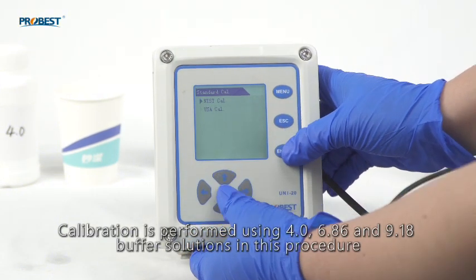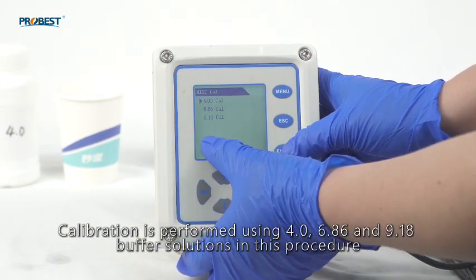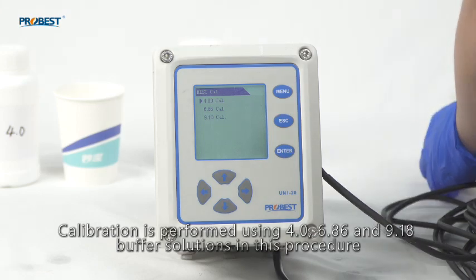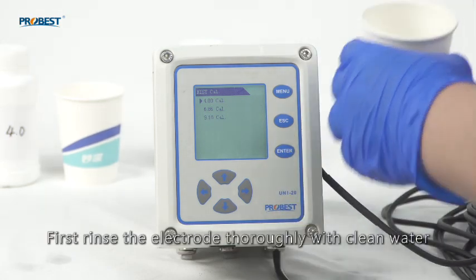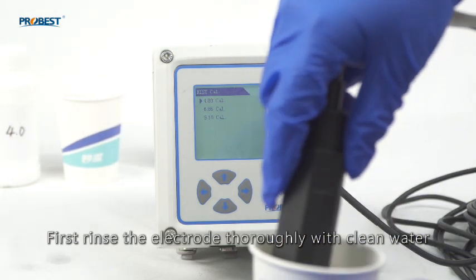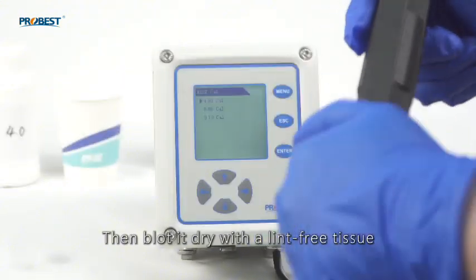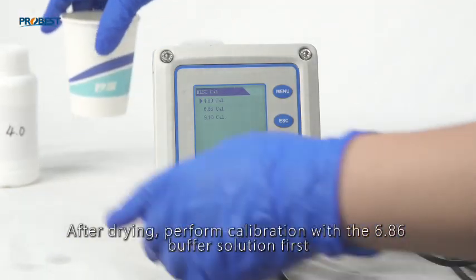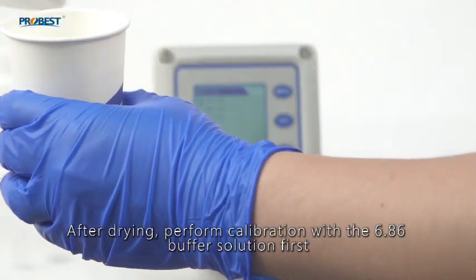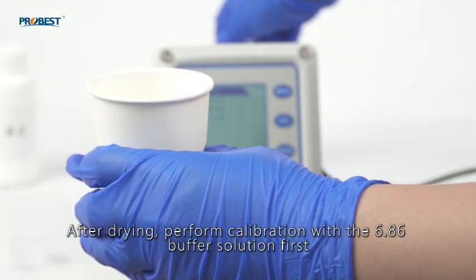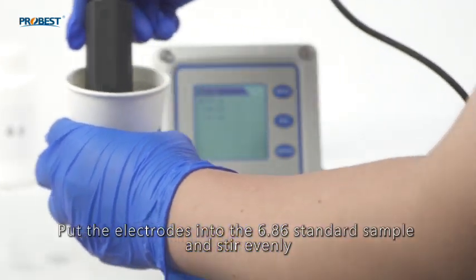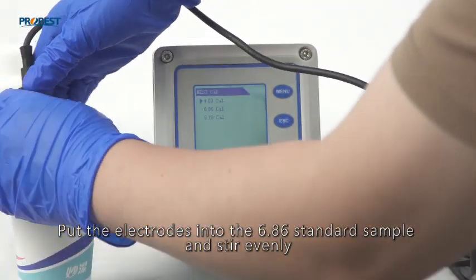Calibration is performed using 4.0, 6.86, and 9.18 buffer solutions in this procedure. First, rinse the electrode thoroughly with clean water. Then blot it dry with a lint-free tissue. After drying, perform calibration with the 6.86 buffer solution first. Put the electrodes into the 6.86 standard sample and stir evenly.